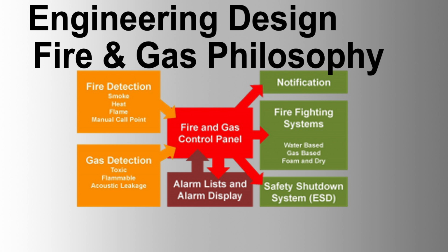General requirements of fire and gas system philosophy. Objective. The fire and gas detection system is provided based on the Project HSE philosophy and fire and gas philosophy documents. The system's primary goal is to monitor all areas handling flammable, toxic, or asphyxiant materials, providing early detection and alerting operating personnel. This includes activation of alarms, initiation of executive actions for emergency shutdown, and depressurization to mitigate risks to personnel, equipment, and the environment.